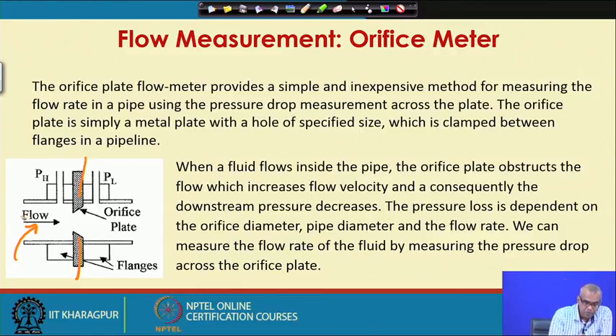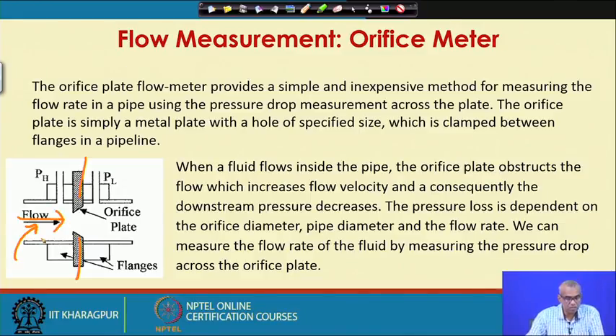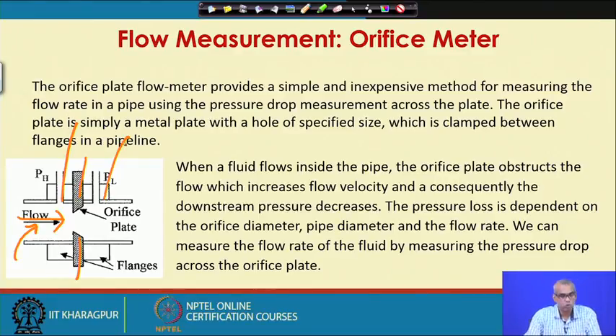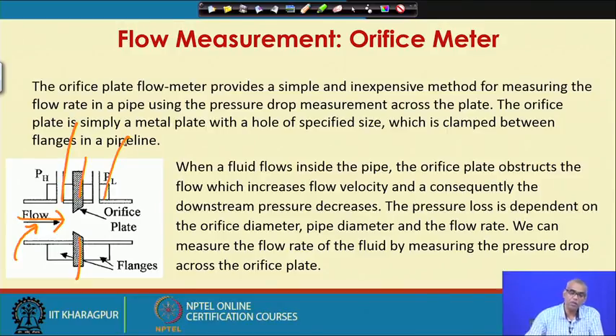When the fluid passes through the orifice plate, as it meets the restriction the velocity increases and consequently the pressure decreases. There is one connection for pressure measurement and another connection for pressure measurement. We measure the pressure drop across the orifice plate and relate this pressure drop with the flow rate of the fluid.